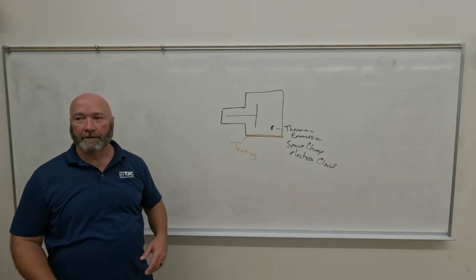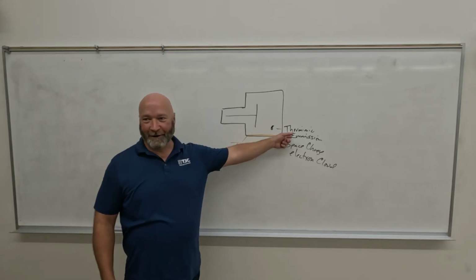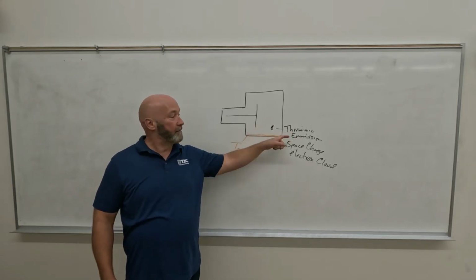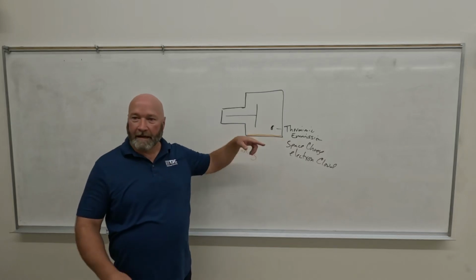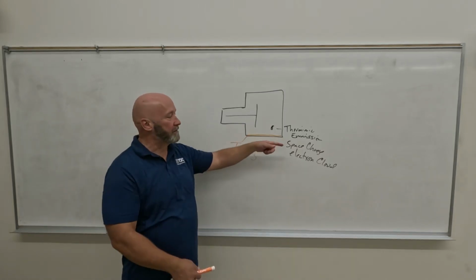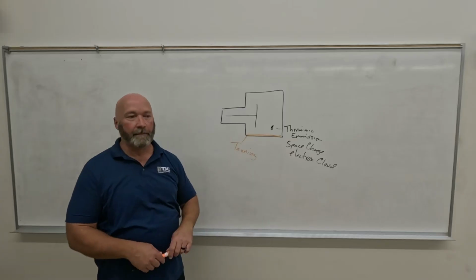So what are we going to have to do? Turn it up a little bit, which is going to make that even hotter. It's going to make more of that. We're going to have a positive feedback system that eventually burns it out, burns the X-ray tube up.